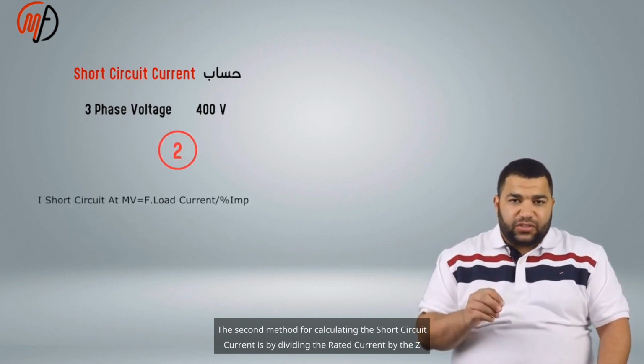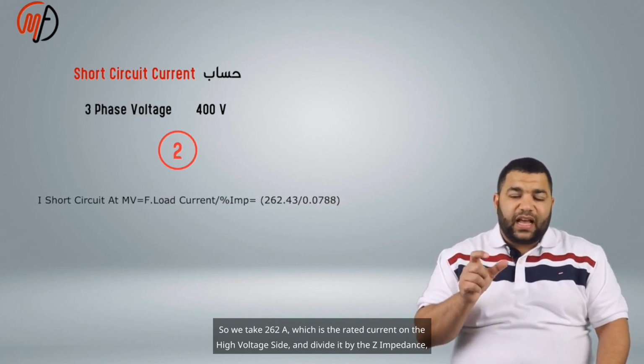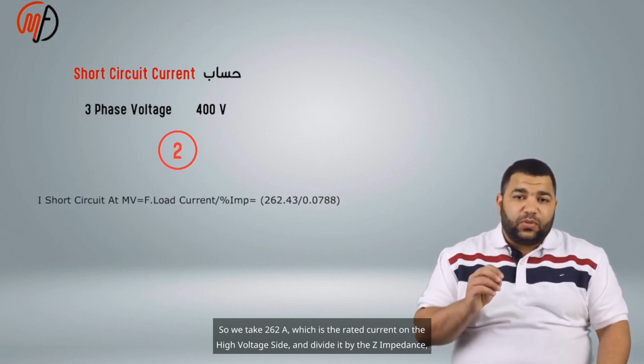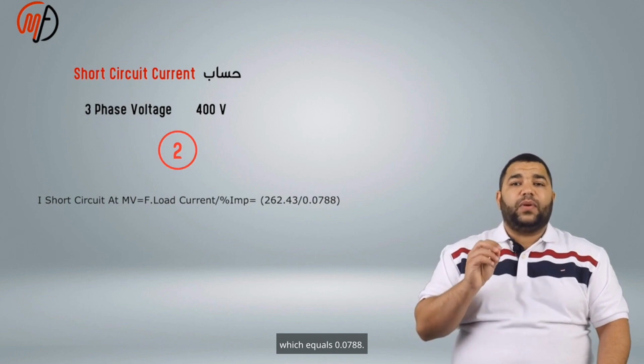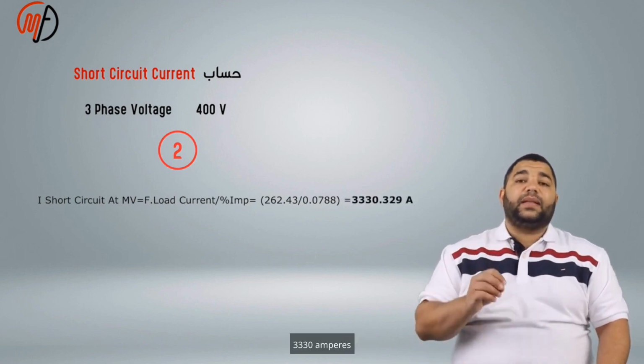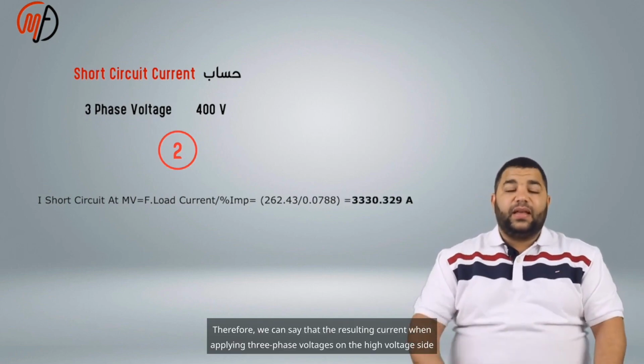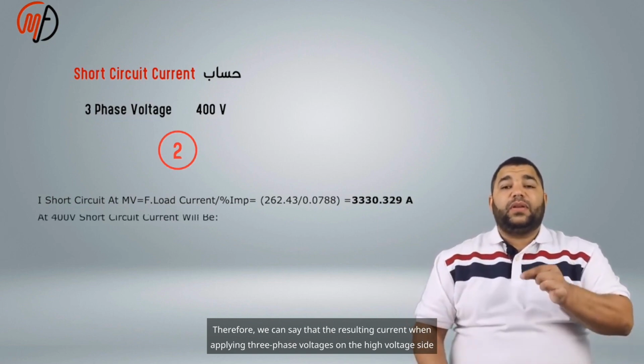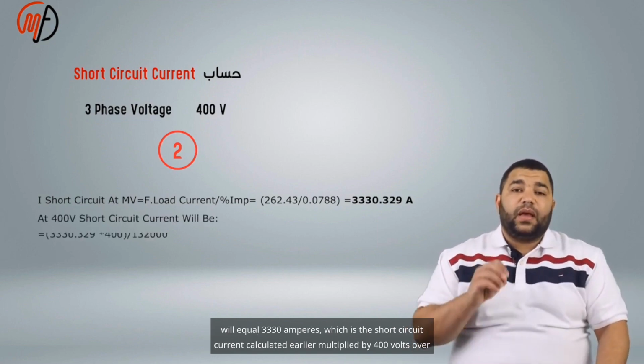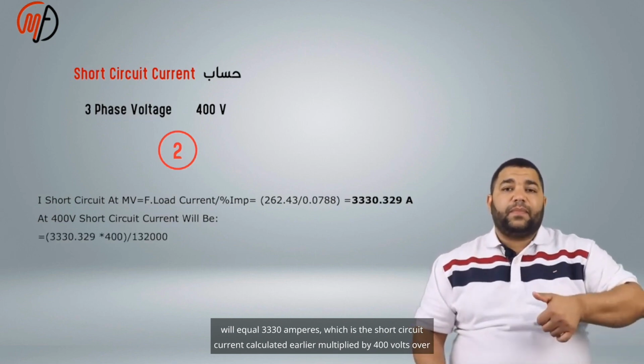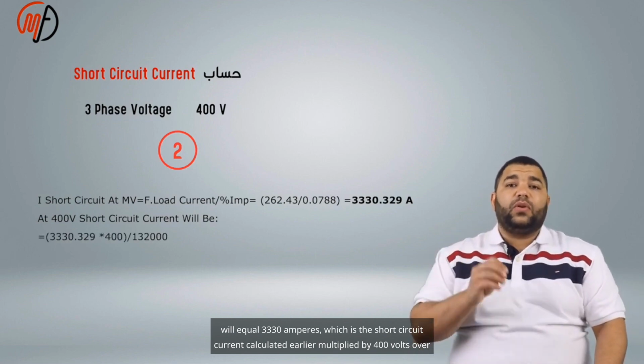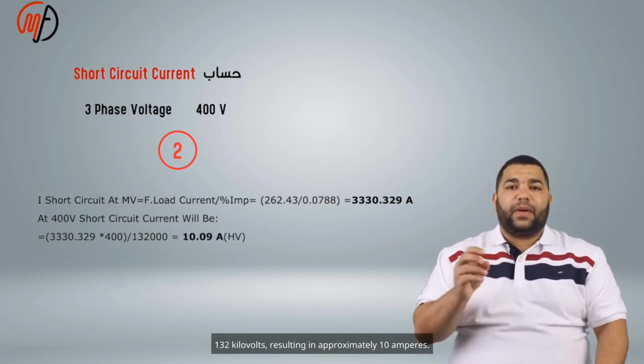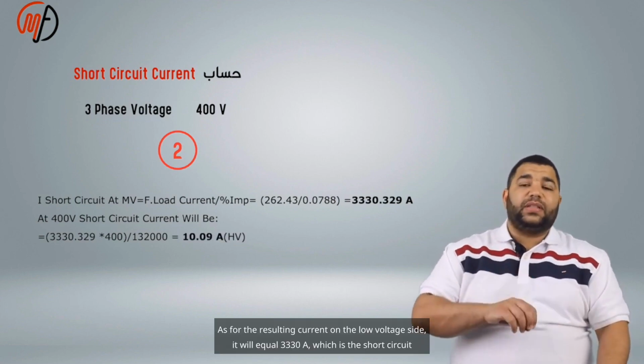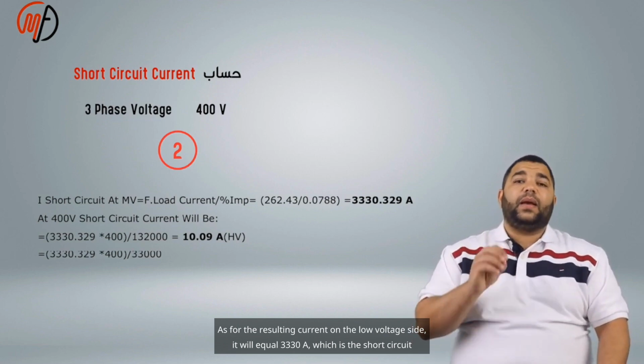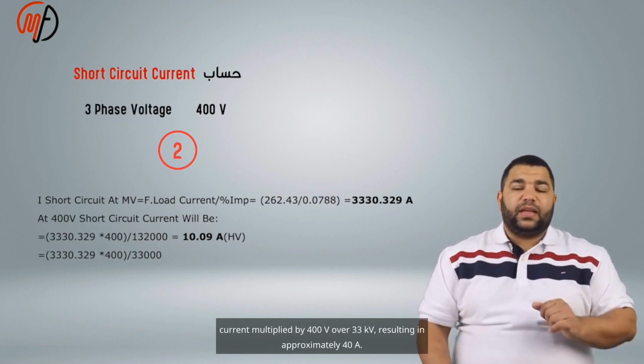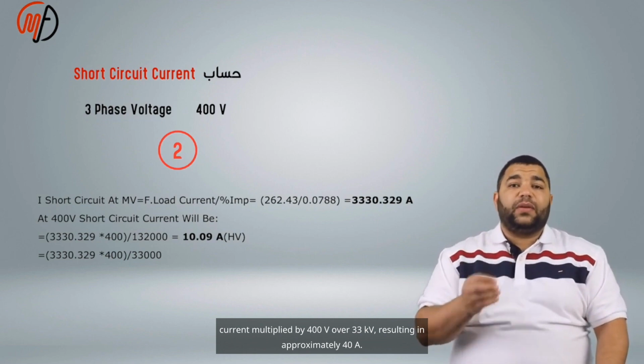The second method for calculating the short circuit current is by dividing the rated current by the Z impedance. So we take 262A, which is the rated current on the high voltage side, and divide it by the Z impedance, which equals 0.0788. The result will be 3330A. Therefore, we can say that the resulting current when applying three-phase voltages on the high voltage side will equal 3330 amperes, which is the short circuit current calculated earlier, multiplied by 400 volts over 132 kilovolts, resulting in approximately 10 amperes. As for the resulting current on the low voltage side, it will equal 3330A, which is the short circuit current, multiplied by 400 V over 33 kV, resulting in approximately 40A.